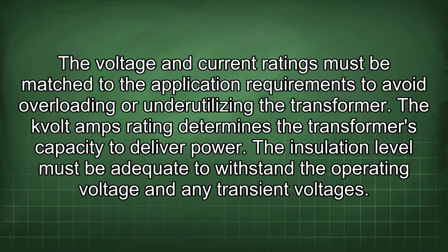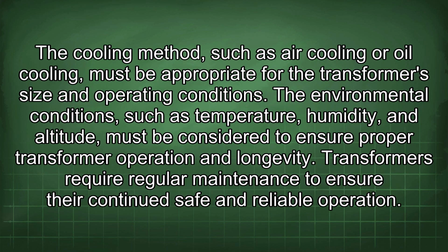The voltage and current ratings must be matched to the application requirements to avoid overloading or underutilizing the transformer. The kVA rating determines the transformer's capacity to deliver power. The insulation level must be adequate to withstand the operating voltage and any transient voltages. The cooling method, such as air cooling or oil cooling, must be appropriate for the transformer's size and operating conditions. The environmental conditions, such as temperature, humidity, and altitude, must be considered to ensure proper transformer operation and longevity.